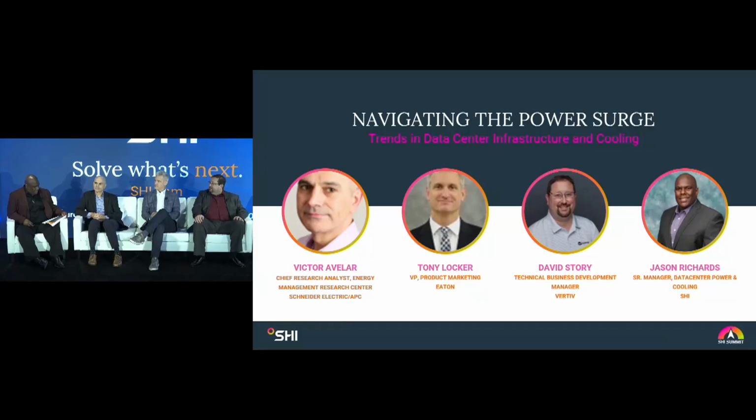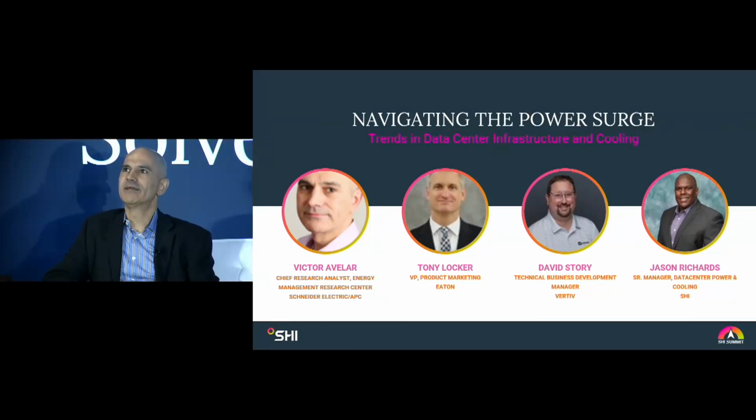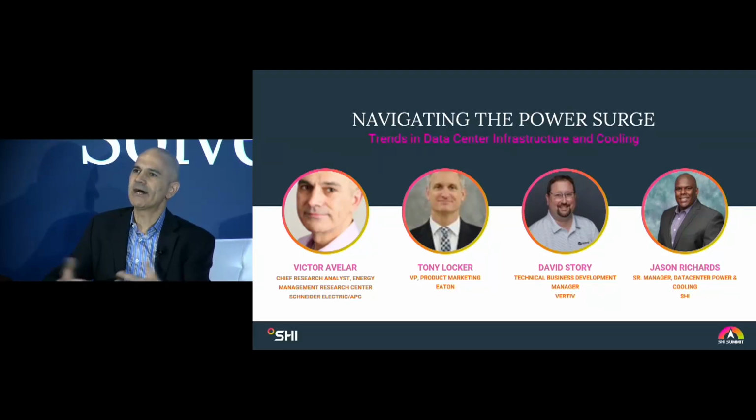All right, so sustainability, you could say it's environmental or social or governance, but I think we want to focus on environmental, and to deep dive a little more, what's the metric for environmental? People tend to think carbon emissions. Carbon emissions in totality can be broken out into three scopes, scope 1, 2, and 3. Scope 1 is what you emit on site, like a generator. Scope 2 is what energy you consume and what emissions come from that energy. Mostly it's electricity for data centers. And then scope 3 is supply chain, embodied carbon in the UPSs and the chillers and the IT equipment.